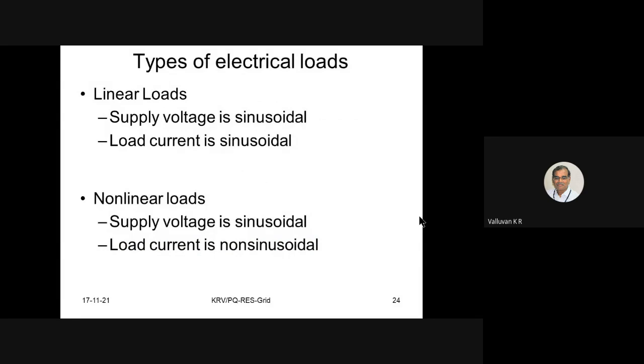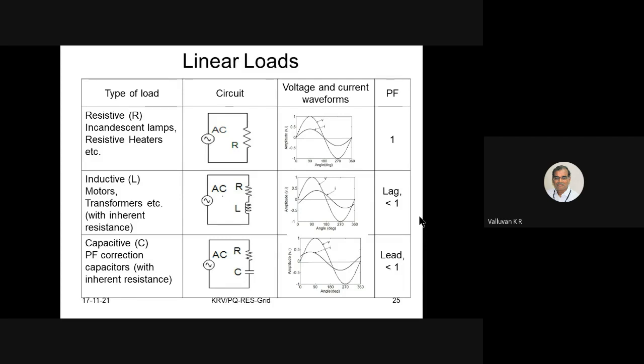Why are harmonics created? Because of non-linear loads. Some of you may know that there are two types of loads, linear loads and non-linear loads. Linear loads are those loads which draw current in the sinusoidal form. The supply voltage is sinusoidal, and the current is also sinusoidal. For non-linear loads, the supply voltage is sinusoidal, but the current is non-sinusoidal. I'll show you some pictures. These waveforms are very familiar to all of us. As electrical engineers, we know that the first graph is for a resistive load. Both voltage and current are in phase. The second waveforms are for inductive loads, where the current lags the voltage. The third one is for capacitive loads, where the current leads the voltage. Though they are lagging or leading, the wave shapes are sinusoidal. Both voltage and current are sinusoidal.